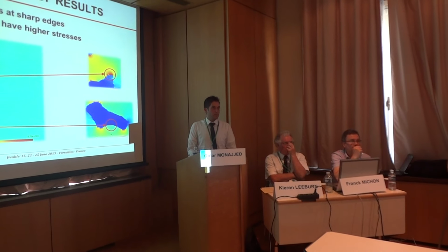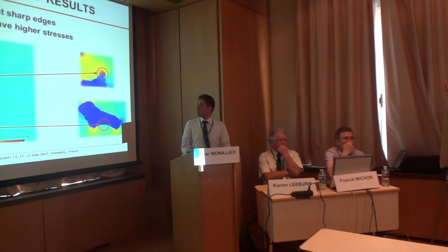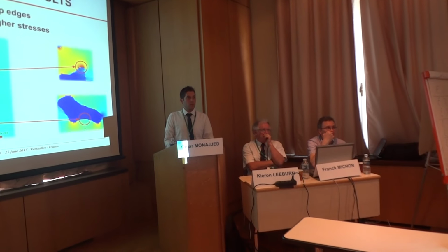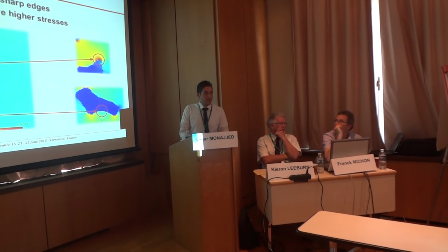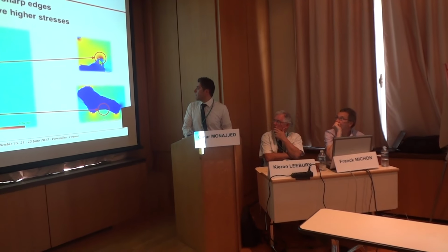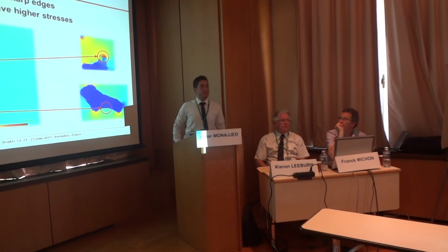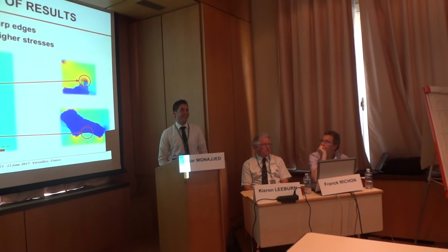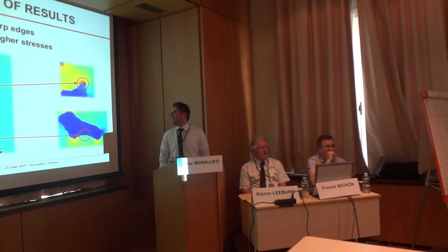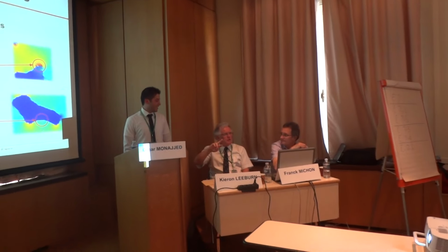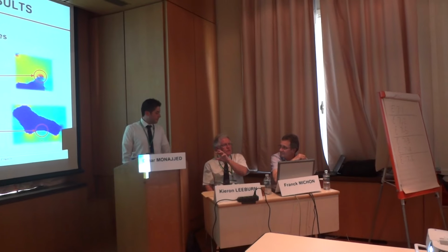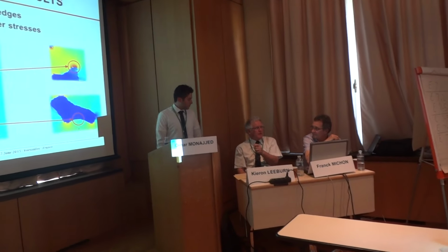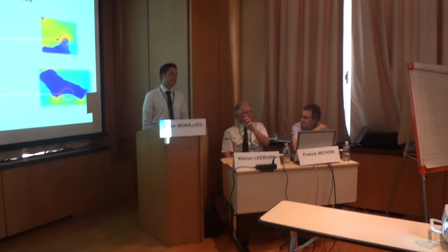But I think in a void close to the area where you have the electric stress between the impurity and the XLPE, and this region, for instance where you have that circle, exactly in the middle, if you have there a void, a shrinking void, then it will be critical, right? And I think the stress is enhanced by the ratio of the permittivity. Sure. So by having an 8 relative permittivity next to a 1, it's worse than having a 2.5 next to a 1.